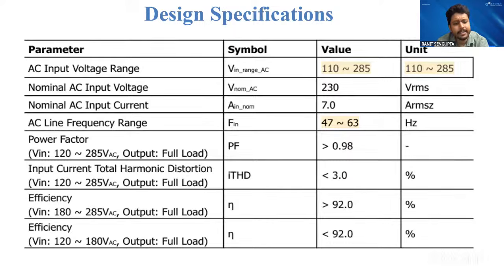Obviously, whenever there is a lower input voltage - we know power is constant - if we decrease the voltage, taking input voltage on the lower side, the current will increase on the input side. So if current increases, depending on overall impedance, there would be losses, meaning I-square-R losses. And within this full operating range, the range is quite big, from 110 to 285.